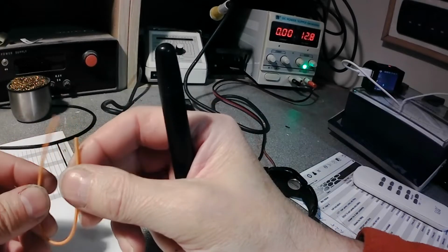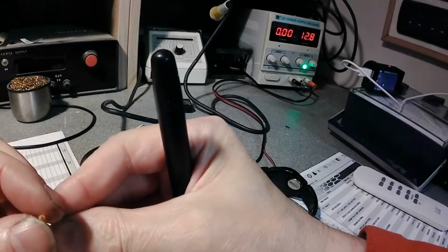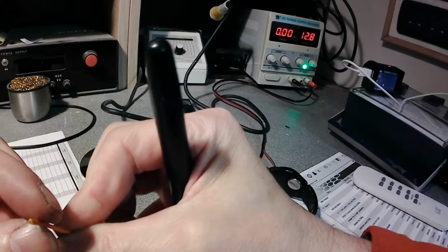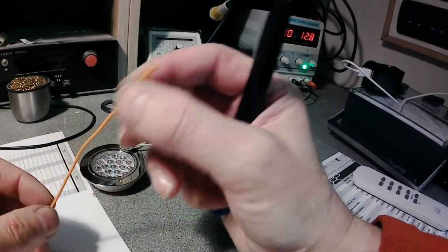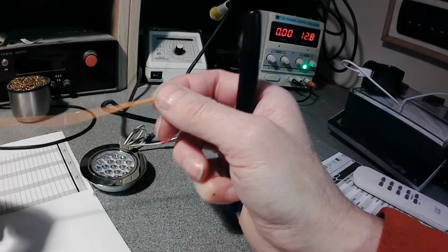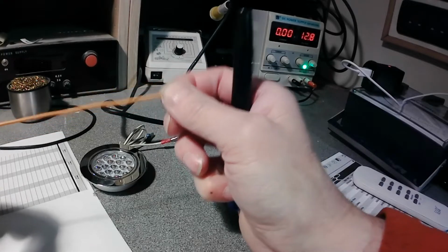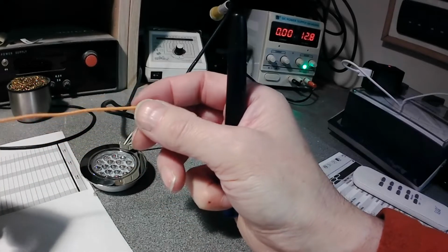And no, because this is a thin wire, the isolation on this wire is quite thin. If we send 16.5 amps through this wire, this isolation will be on the verge of melting. And second, there is something like a voltage drop.